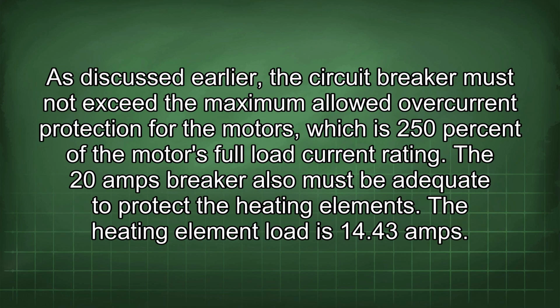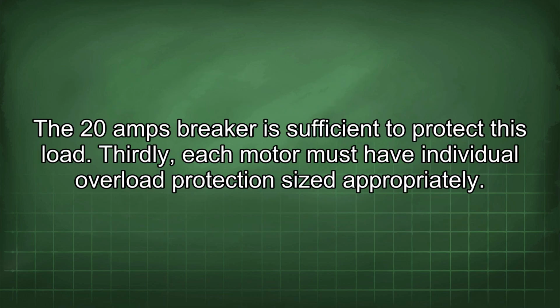As discussed earlier, the circuit breaker must not exceed the maximum allowed overcurrent protection for the motors, which is 250% of the motor's full load current rating. The 20 amp breaker also must be adequate to protect the heating elements. The heating element load is 14.43 amps. The 20 amp breaker is sufficient to protect this load.